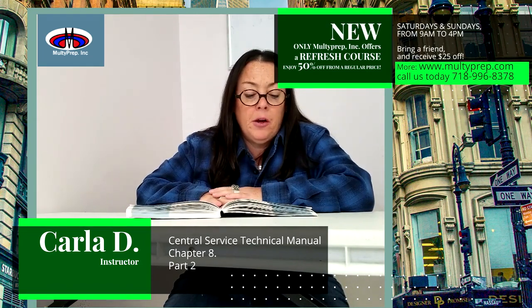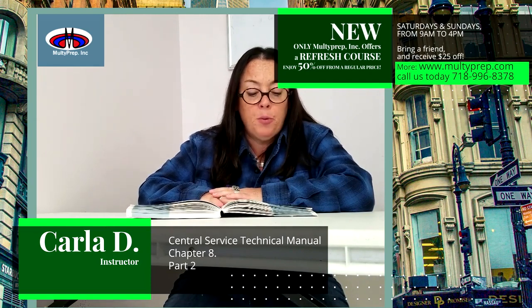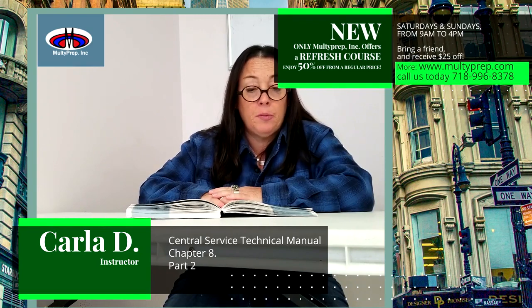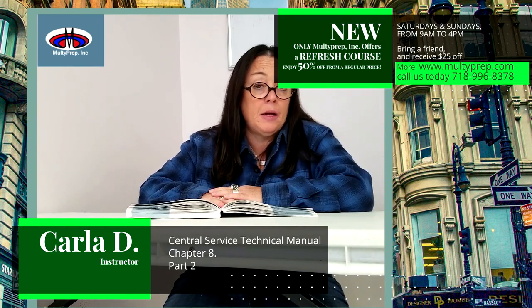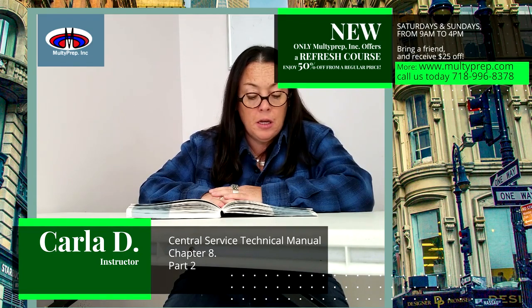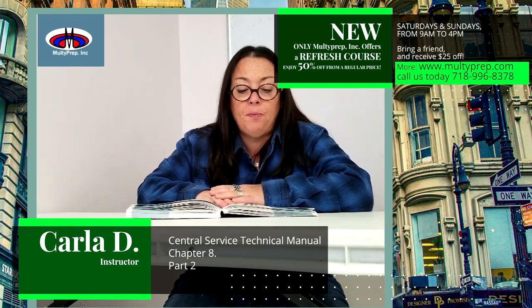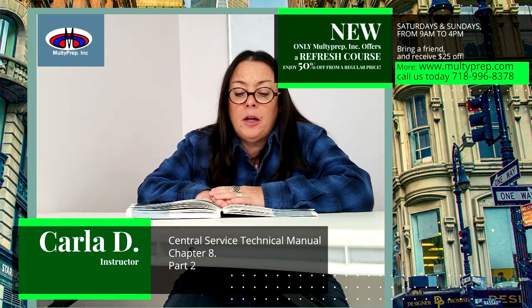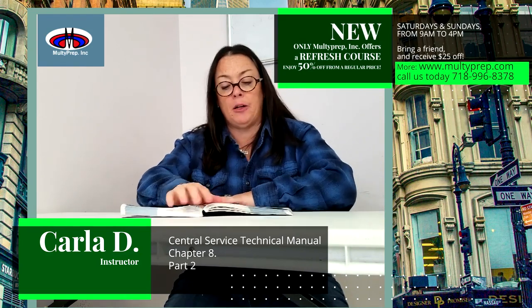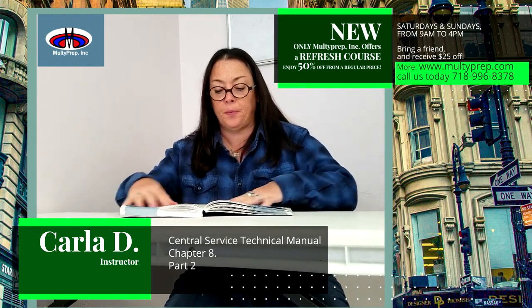Thoroughly cleaning and adherence to IFUs is important because failure of the cleaning process puts patients and staff at risk. There are several types of cleaning methods. Pre-cleaning: this process should occur at the point of use. Manual cleaning, also known as cleaning by hand. Mechanical cleaning: cleaning items using specialized cleaning equipment. The method of cleaning selected should follow the device manufacturer's instructions for use.